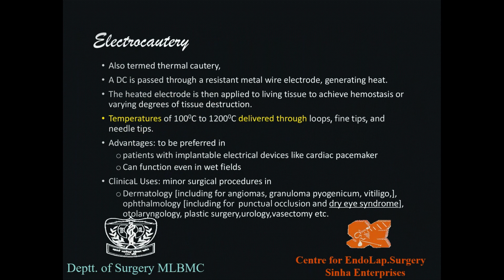Okay. Now, coming back to what is electrocautery, which we commonly use interchangeably with electrosurgery. Where is the cautery machine? Put the cautery on, press the cautery button, and so on and so forth. So what we're talking about here is basically a thermal cautery. Why? Because it heats and that heat gets transferred to the body. A direct current passes through a resistant metal wire electrode which generates the heat. That heated electrode is then applied to the living tissue to achieve hemostasis or varying degrees of tissue destruction.